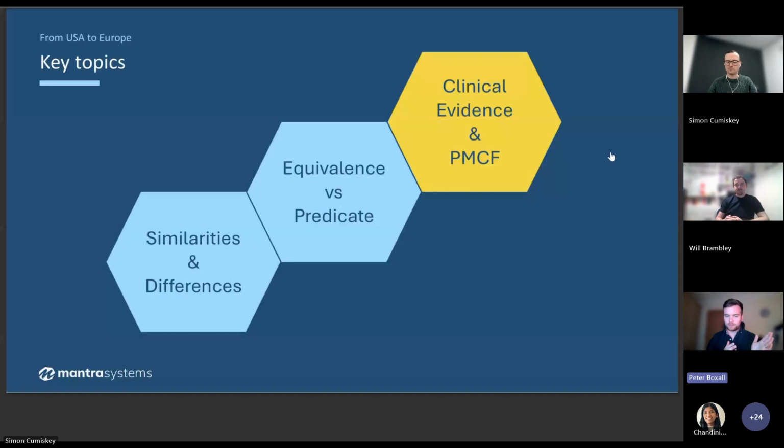Really, it's important, as we said, to plan early and to understand each of the steps of using clinical evidence. So when we know our intended purpose, we know the performance and safety objectives that we need to generate through a state-of-the-art literature review. Once we know what those objectives are, we know the clinical evidence that we need to support suitability of our own device.